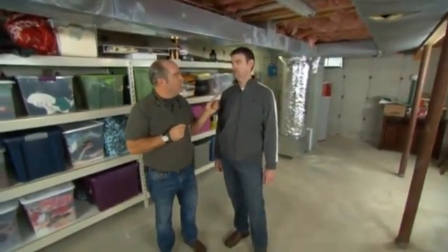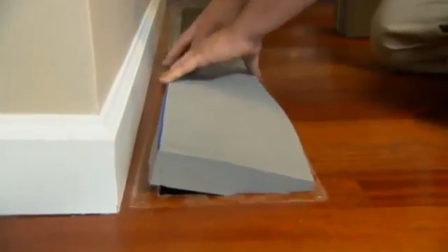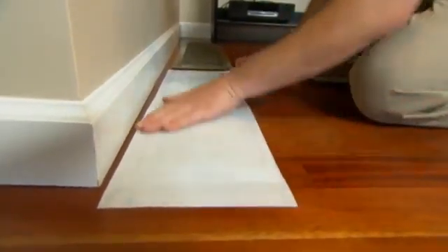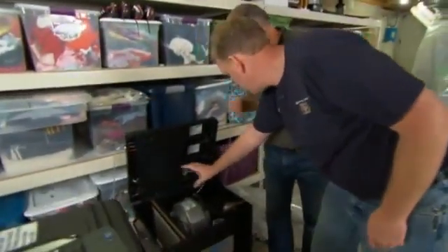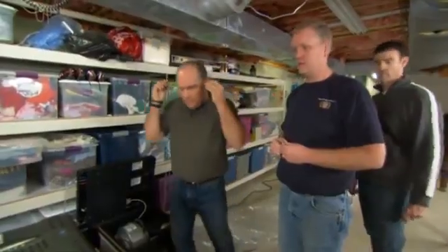What I actually want to do is show a technology where we can seal every bit of this duct work perfectly from the inside. This is Mark Saleh — I'm Steve Taylor. He's going to help us seal the ducts today. We've already started upstairs. We've sealed all of the supply and all of the return registers. Any leakage we measure now is coming just from the duct work. Then you tested the ducts? We did. We ran a pre-test, using the fan in this box to blow air into the duct system and see how much air leaks out through the duct. That pressurized the ducts and tied into the computer here.